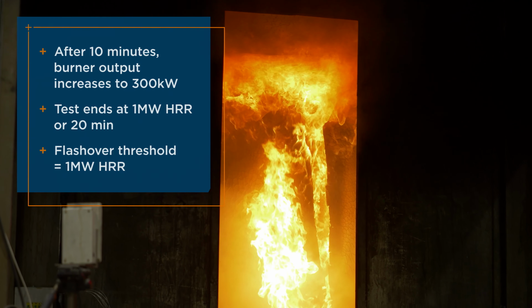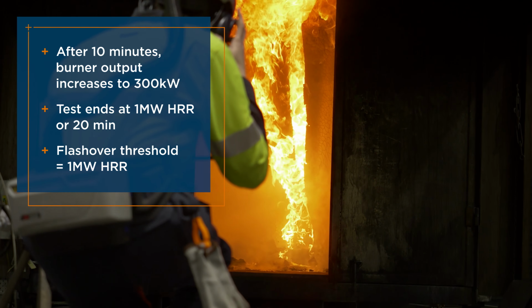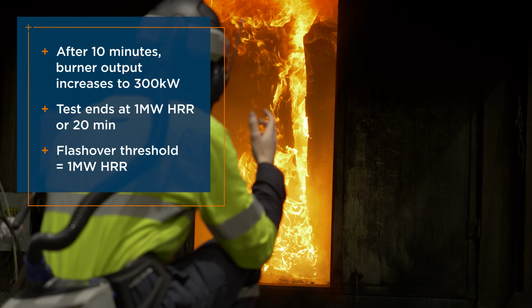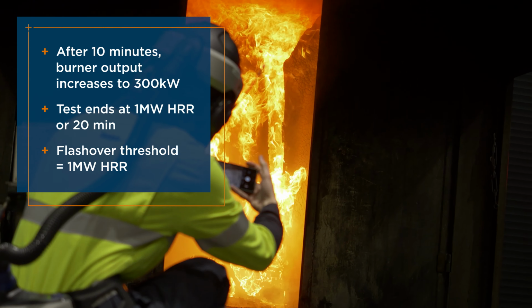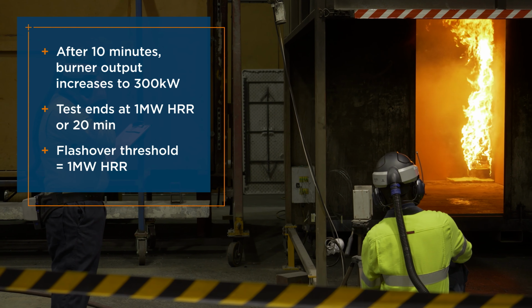After 10 minutes of this initial exposure, the burner output is increased to 300 kilowatts and the observations and measurements continue for a further 10 minutes. The exposure is stopped after 20 minutes. However, the test may be concluded earlier if the total heat release rate exceeds 1 megawatt, which is considered empirically to be the onset of a flashover fire.